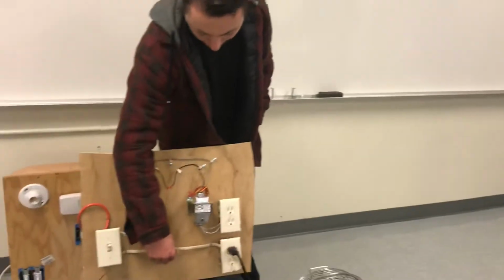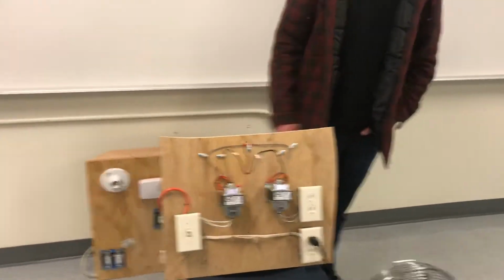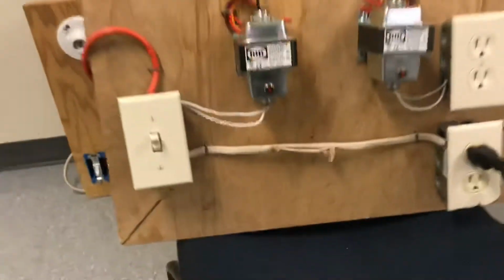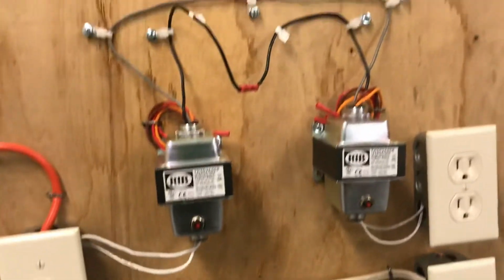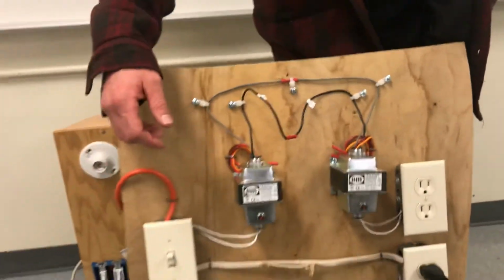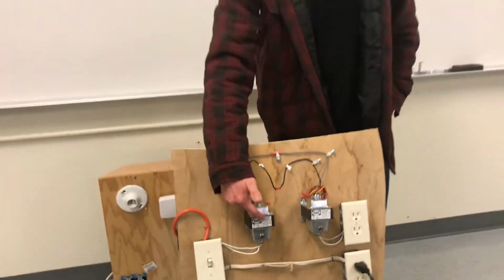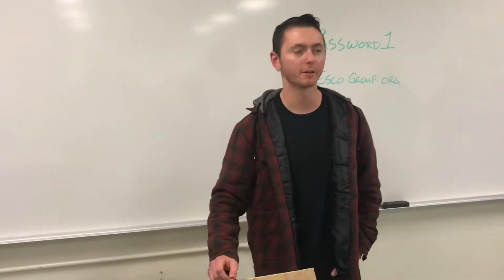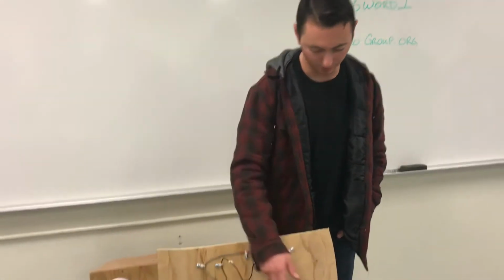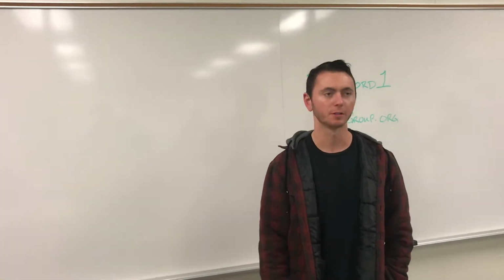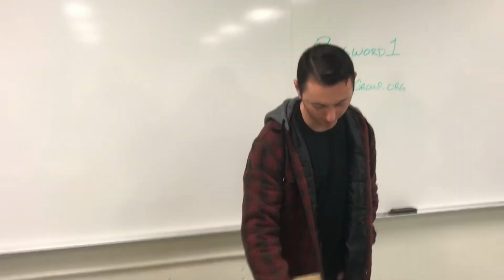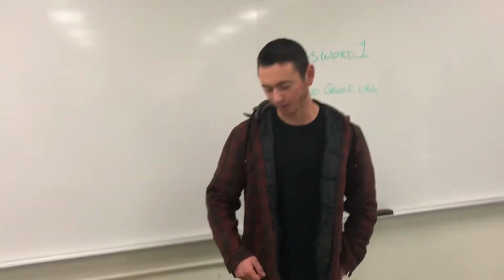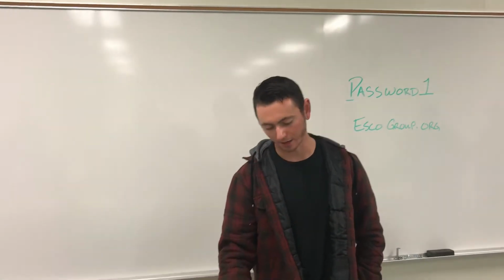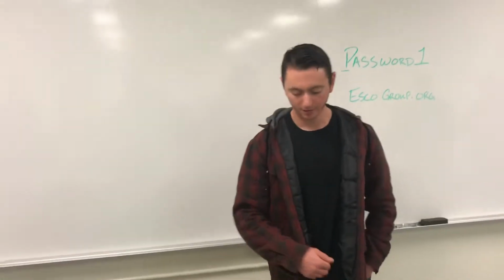I stripped a little bit of it so that we can use a clamp-on ammeter to see how much amps are being drawn. The second circuit goes to a step-up transformer. It steps it up to 480 volts, and then it goes back to a step-down transformer, which steps it back down to 120 volts, so that we can plug it into this receptacle and see the amp draw on this circuit instead.